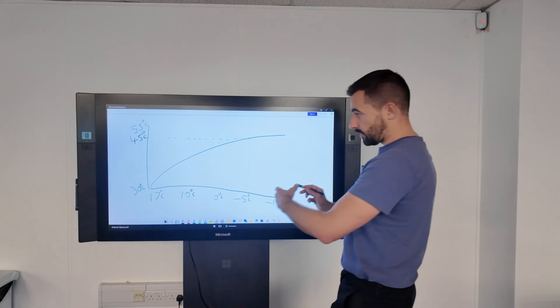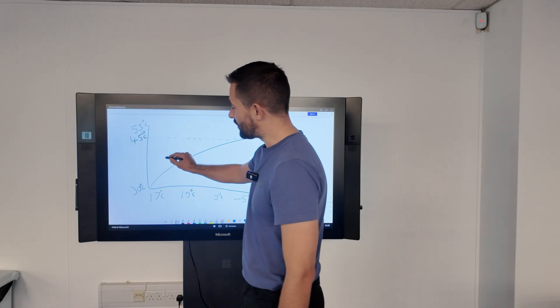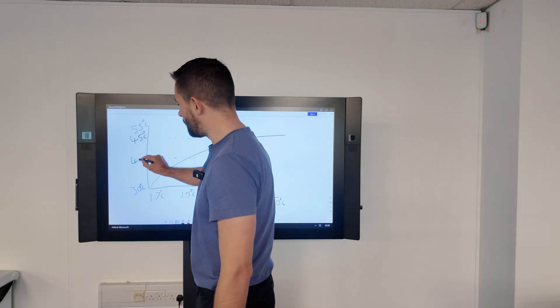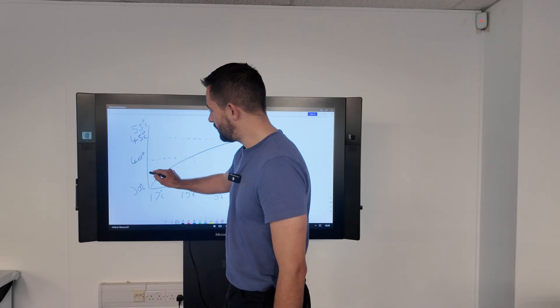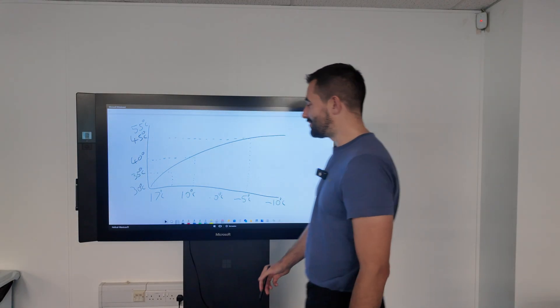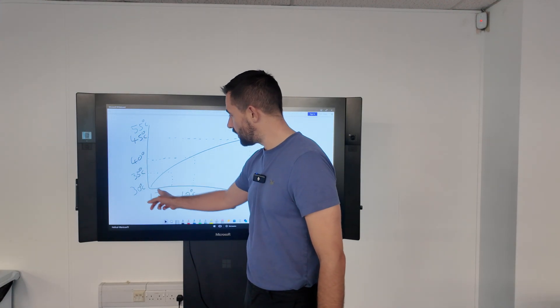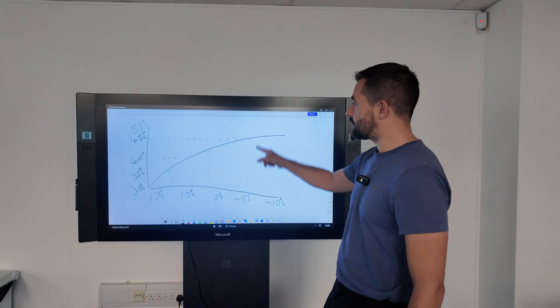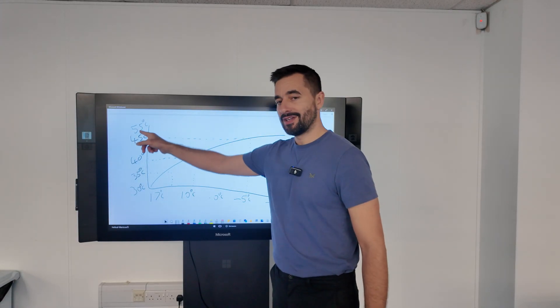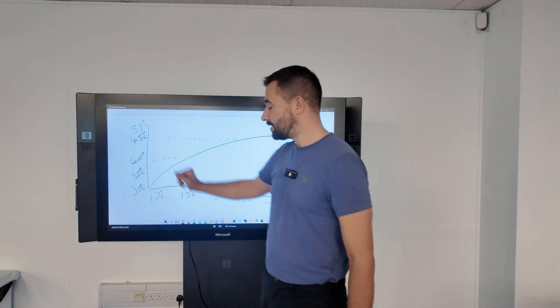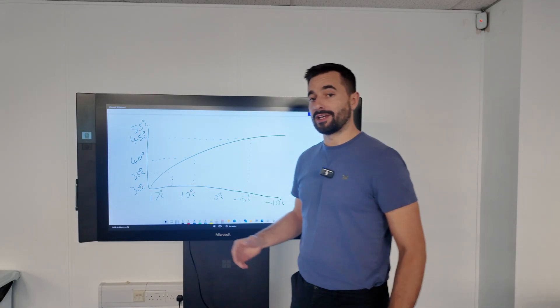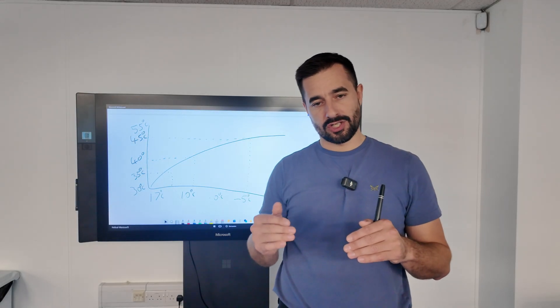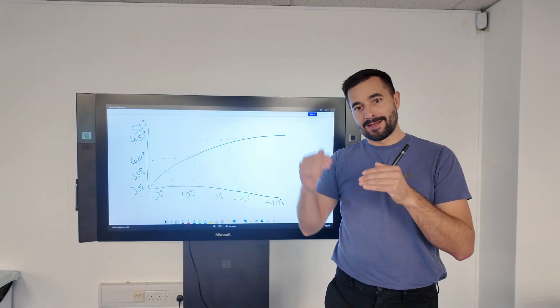As you imagine, as we're getting warmer, the flow temperature will be lower. Warmer still, flow temperature cooler. So the warmer it is outside, the cooler the flow temperature. The colder it is outside, the hotter the flow temperature. When it's really cold outside, your radiators will feel hot. And when it's warmer outside, they'll feel cooler.